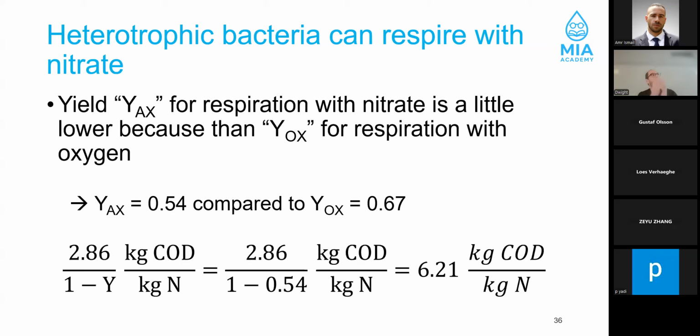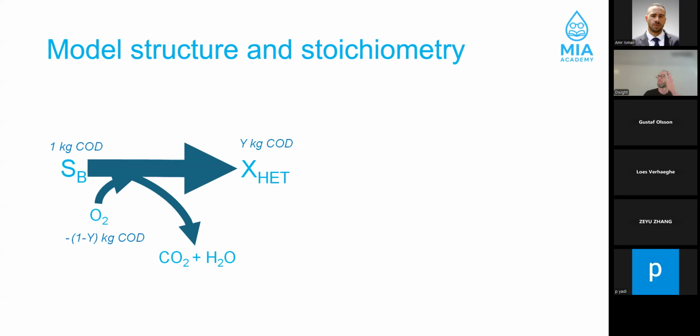So this is already showing a little bit how we can use these models to come up with interesting engineering relationships. And it highlights that actually removing nitrate is hard. It takes a lot of carbon. So if you're operating a process where you want to do nitrogen removal, you're going to need a lot of carbon. And the carbon that's coming in your influent from the sewer system, you might want to use that very judiciously. Okay, so back to our arrows. There you go, Peter. I told them how many kilograms of COD you require to remove nitrate.